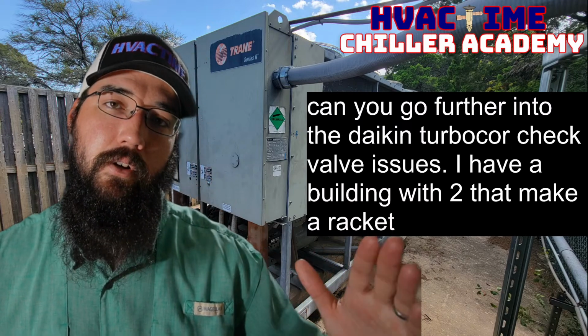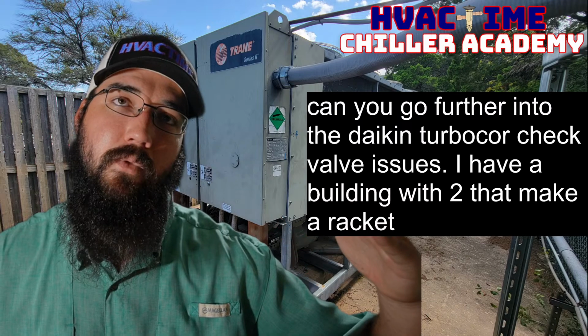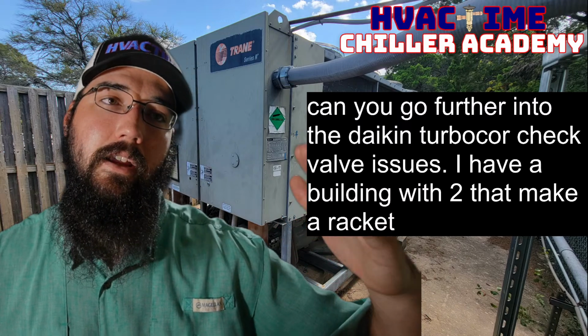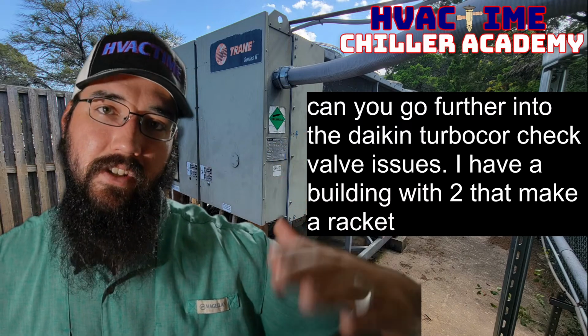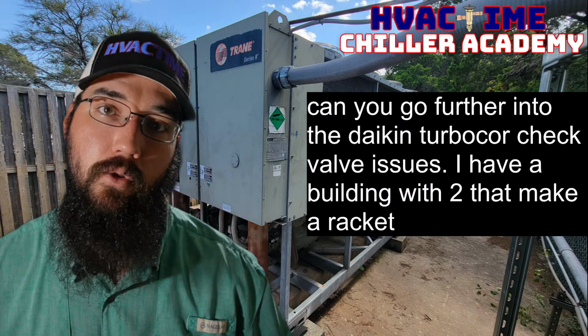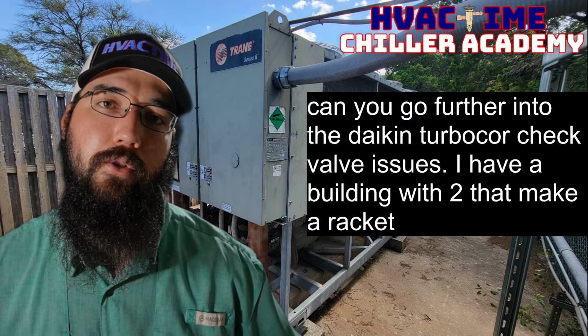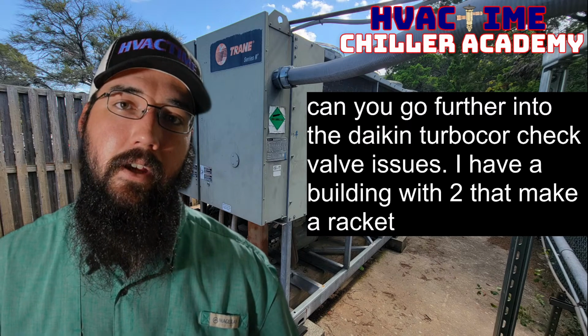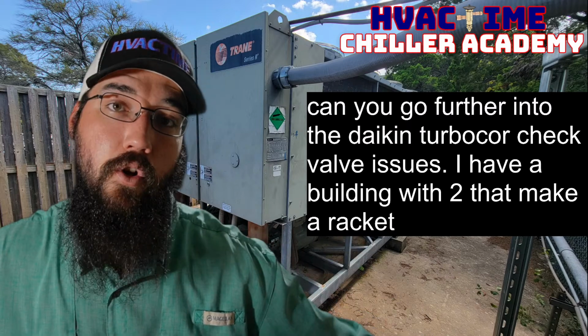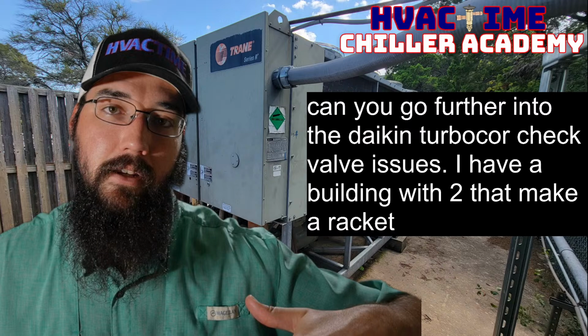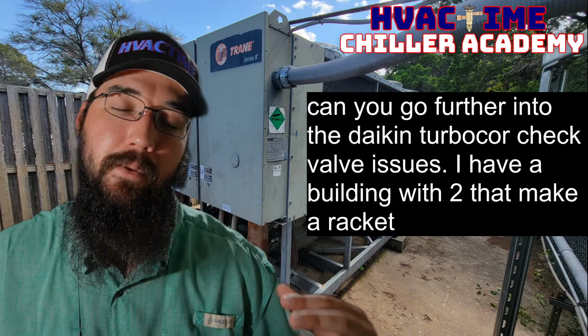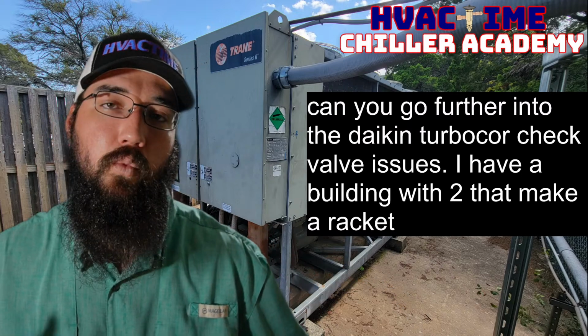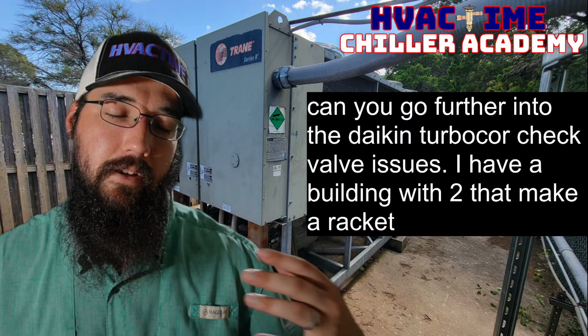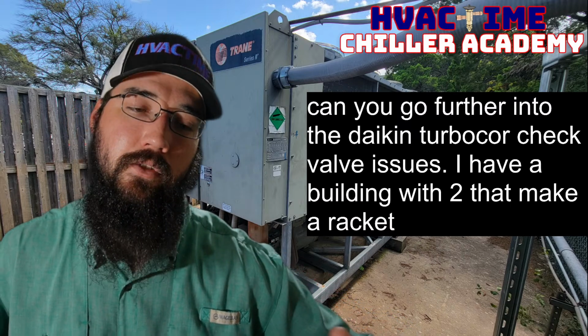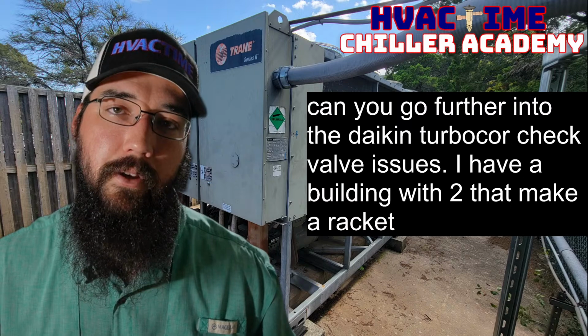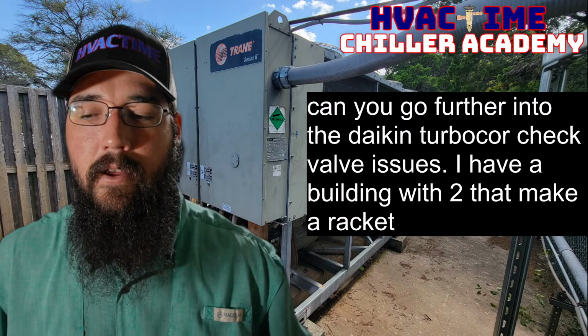Another failure was, especially when they had the gate style, that gate would actually snap at the hinge, and then it would just block the whole discharge line. And so you'd go to try to spin up, and the discharge couldn't open because it had blocked itself off, because it had snapped off inside of there off of the armature. So that was one of the failures that was happening. Either shrapnel sent to the condenser, or it just completely stopped flowing discharge gas altogether.